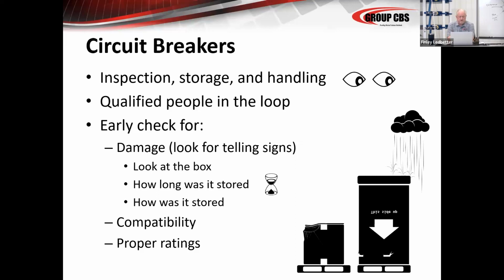So in the early check, look for damage on the boxes, look for discoloration on the boxes. When the breakers come out of the crating to go into the switchgear, be sure there's someone there that can visually take a look at them and make sure not only are they in clean, good condition, but they haven't been damaged and they're properly prepared. You'll also find breakers that are missing components. So it's very important to do those initial inspections and tests. How long was it stored and how was it stored? Two good things you have to know.